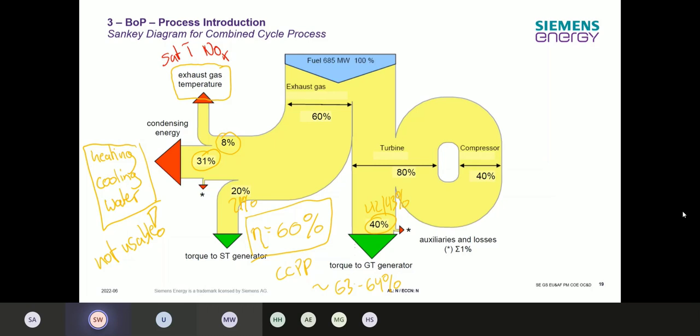They will stick on there, lead to corrosion, and damage the piping, so we want to keep the exhaust gas temperature above the saturation temperature of the NOx gases. This is normally, I would say, somewhere above 55 degrees or something. Somewhere in this area.